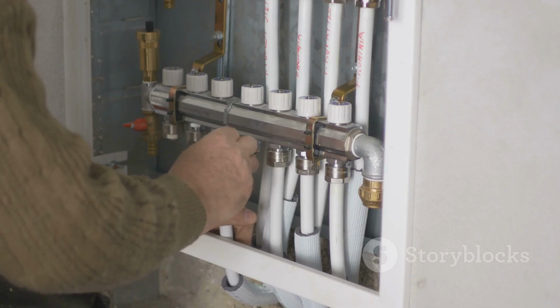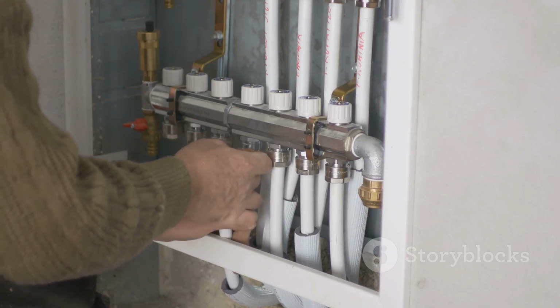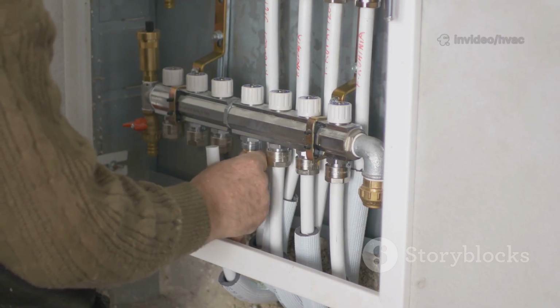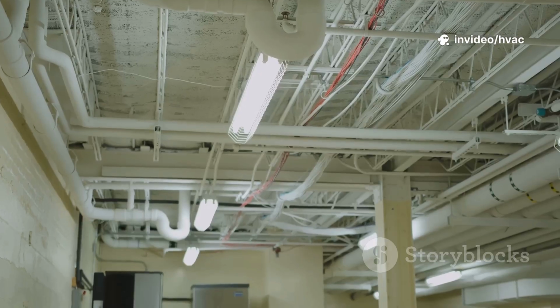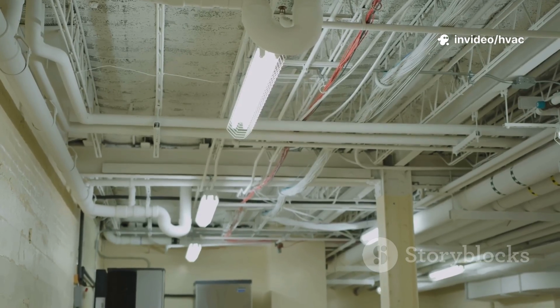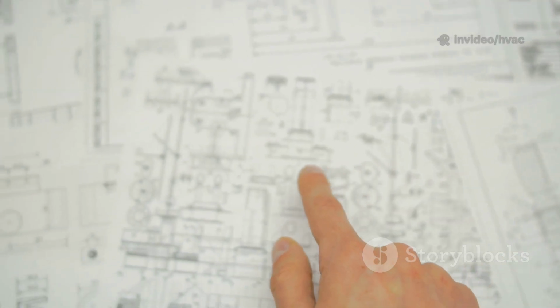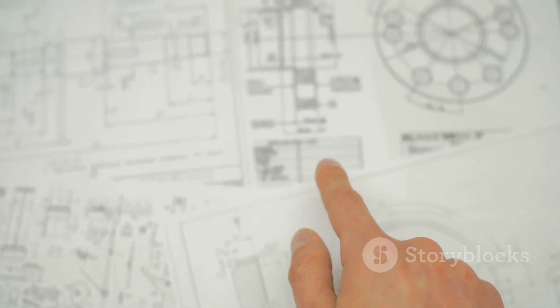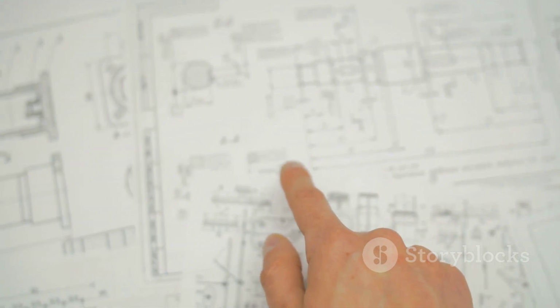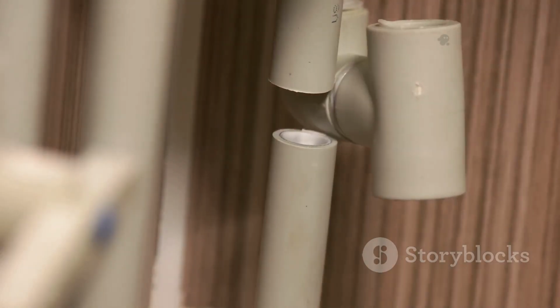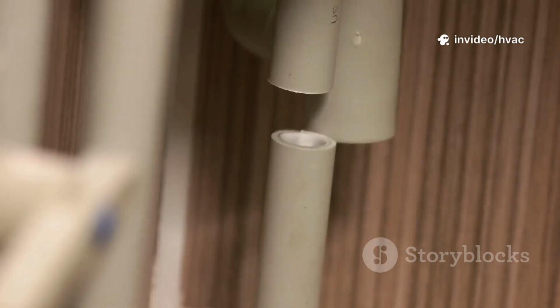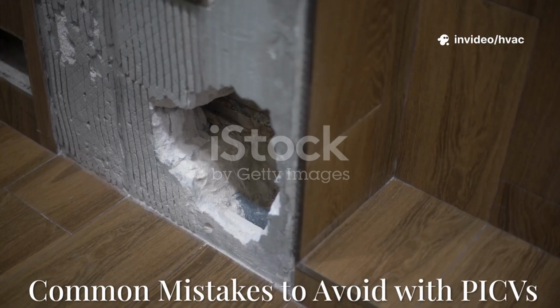Technicians also need physical space around the valve to get their hands and tools in to make adjustments to the flow setting dial or to perform service. Sometimes valves are installed in tight ceiling spaces or behind access panels. It's the installer's responsibility to ensure the PICV is positioned in a way that allows for easy access later on. Planning for this during the initial installation will save a lot of time and frustration during future maintenance activities.